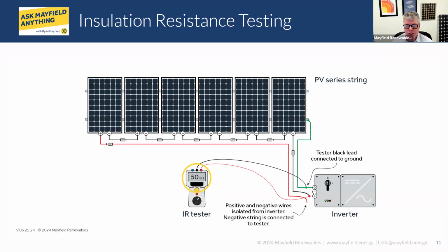Yeah, thanks for that, Chris. So definitely part of the overall troubleshooting process. It was interesting when we were talking right before the webinar started, about the video we're about to show you. We had done some in-field testing as well, and we actually came across a section of the array that had a very low insulation resistance value. We were doing that troubleshooting, but the inverter wasn't returning any faults. So it's interesting to see how these tests can highlight potential problems that are avoidable in the field.